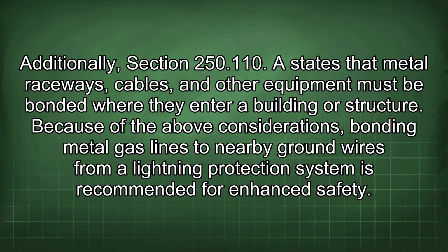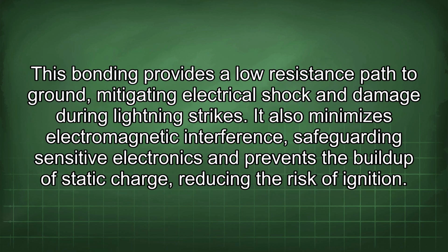Because of the above considerations, bonding metal gas lines to nearby ground wires from a lightning protection system is recommended for enhanced safety. This bonding provides a low resistance path to ground, mitigating electrical shock and damage during lightning strikes. It also minimizes electromagnetic interference, safeguarding sensitive electronics, and prevents the buildup of static charge, reducing the risk of ignition.